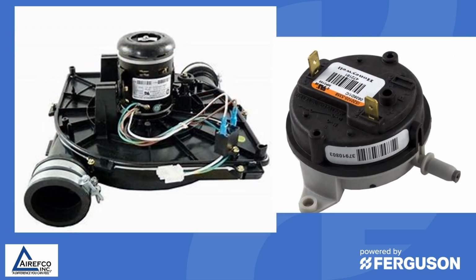The sequence of operation for most gas furnaces is that the induced draft motor starts up first, and then when it gets up to speed, it will close the pressure switch that is monitoring the vent. When the pressure switch closes, then the ignition cycle will start and the burners will light. If anything happens to the inducer motor or anything blocks the vent during the operation of the furnace, this pressure switch will open up and will shut down the furnace.